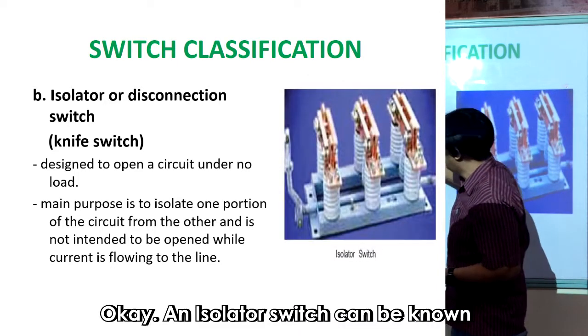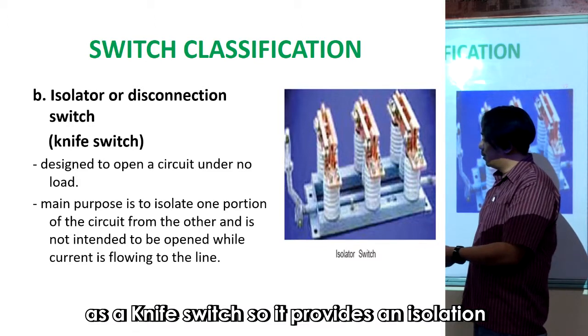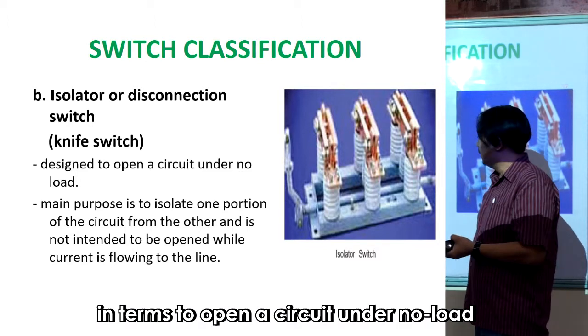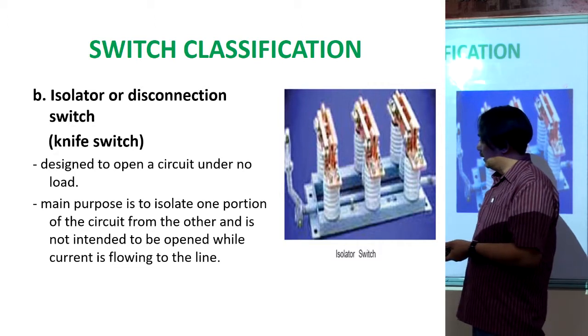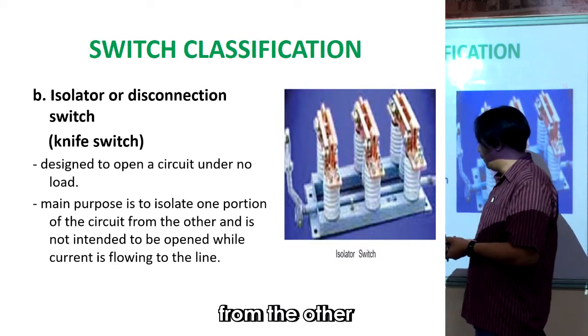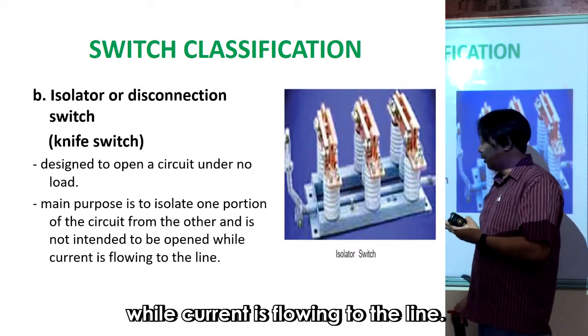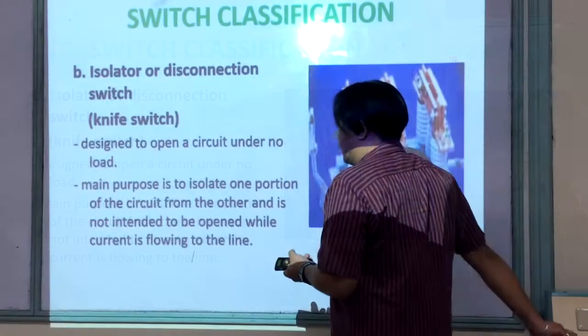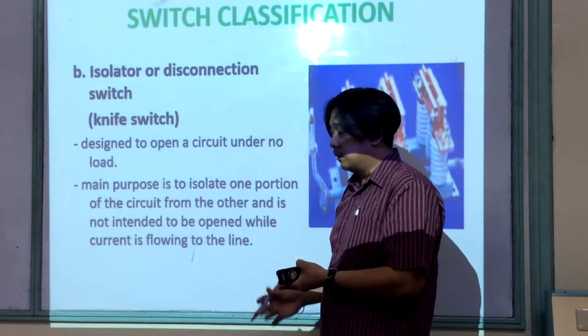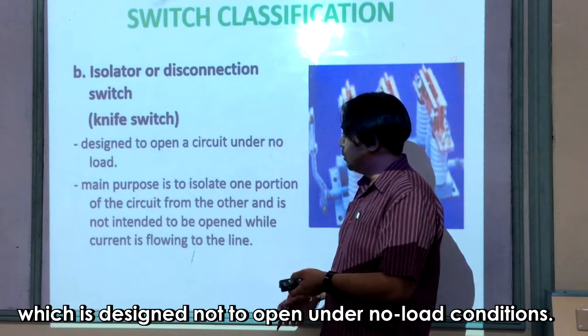An isolator switch, also known as a knife switch, provides isolation by opening a circuit under no load. Its main purpose is to isolate one portion of the circuit from the other, and it is intended to be opened when current is not flowing. It is essentially a low voltage switch designed not to open under load conditions.